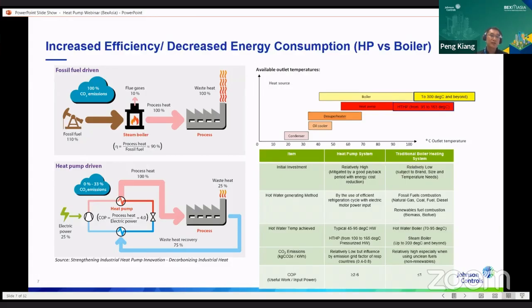For many types of reasons, of course. And if you look at the comparison with a heat pump, the one below in the diagram, you can see that instead of 100% of the energy being converted from fuel, you only use 25% electric power, and the rest, 75% of the energy, comes from a waste heat source. This waste heat source can come from a factory, because in any factory there's always parallel cooling and heating at the same time, and some heat rejection. If you can rechannel this energy back through the heat pump, you can imagine that the efficiency of the heat pump is much higher than that of a boiler. And you can reduce the carbon footprint by going through a heat pump cycle like this, and yet at the same time create 100% of the process heat that you require for the factory.